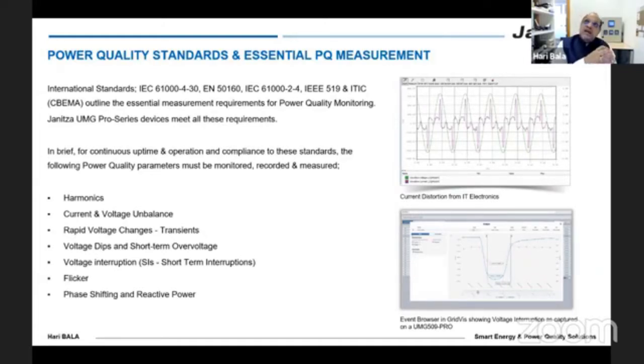In India, as I speak to many customers and consumers across India, IEEE 519 is still a mystery for many of the consumers. Even some utilities would like to implement it, but they do not know how to do it, what to do. So the process of ours today is only to lighten it, to give a glimpse of how it can be done. For continuous uptime operation, compliance to these standards becomes very important with respect to power quality, like harmonics, current, voltage unbalance. Most of these standards talk about parameters like voltage dips, short-term over voltage, interruptions, flicker and phase shifting. So these are all the standards which are available.